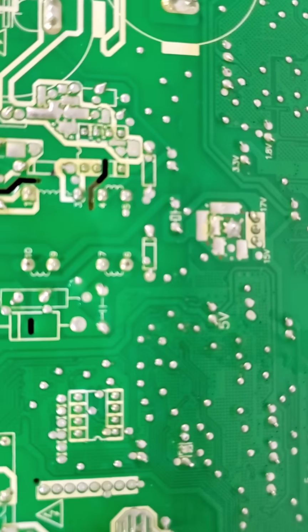If you look at the top of the board, you will have voltage marks on here. Here, see if I can zoom in there so you can read it. 5 volts. So if you read from pin to pin, you should have a dedicated 5 volts constantly on that board. If you don't have that 5 volts, then one of these could actually be your trouble. And it could be just as simple as that. So you might not have a board problem, you could actually have one of your sensors or TXV causing your problem.